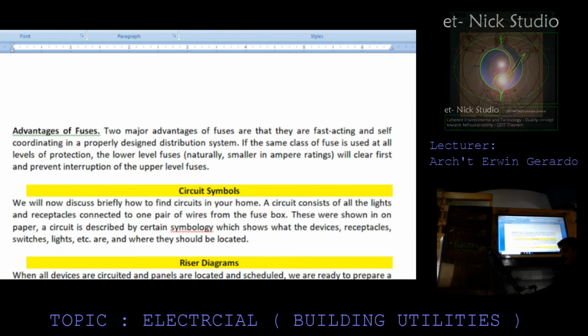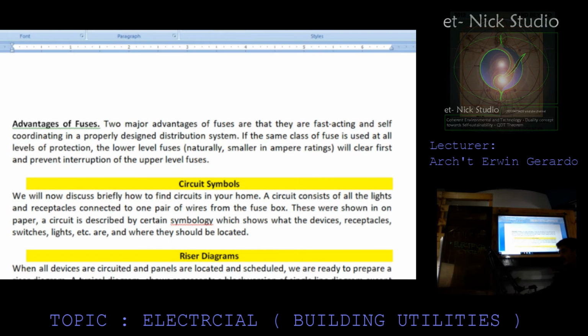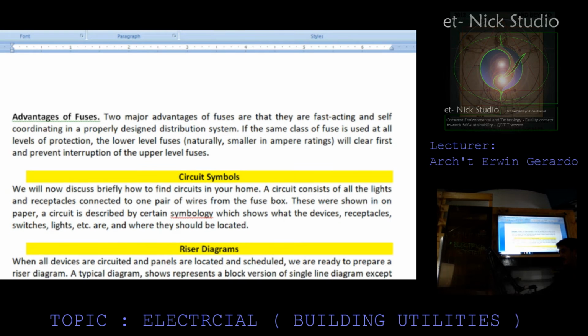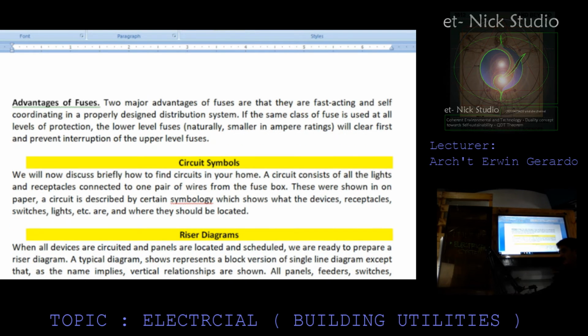Advantages of fuses. Two major advantages of fuses are that they are fast acting and self-coordinating in a properly designed distribution system. If the same class of fuse is used at all levels of protection, the lower level fuses, naturally the smaller in ampere ratings, will clear first and prevent interruption of the upper level fuses.